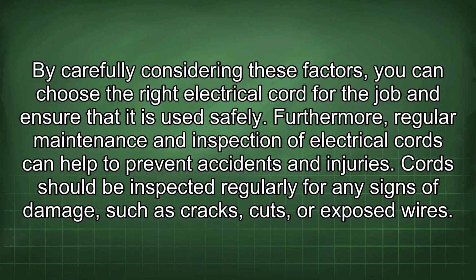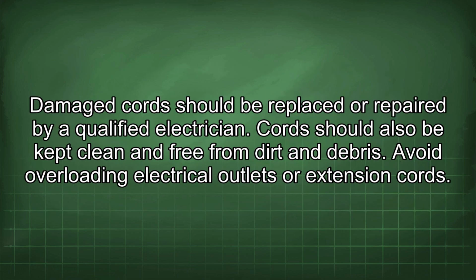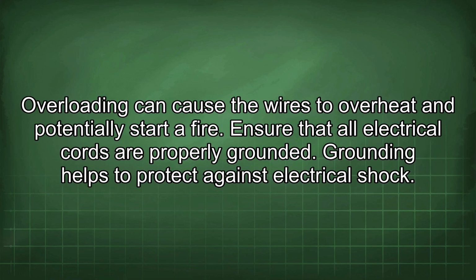By carefully considering these factors, you can choose the right electrical cord for the job and ensure that it is used safely. Furthermore, regular maintenance and inspection of electrical cords can help to prevent accidents and injuries. Cords should be inspected regularly for any signs of damage, such as cracks, cuts, or exposed wires. Damaged cords should be replaced or repaired by a qualified electrician. Cords should also be kept clean and free from dirt and debris. Avoid overloading electrical outlets or extension cords. Overloading can cause the wires to overheat and potentially start a fire. Ensure that all electrical cords are properly grounded. Grounding helps to protect against electrical shock.